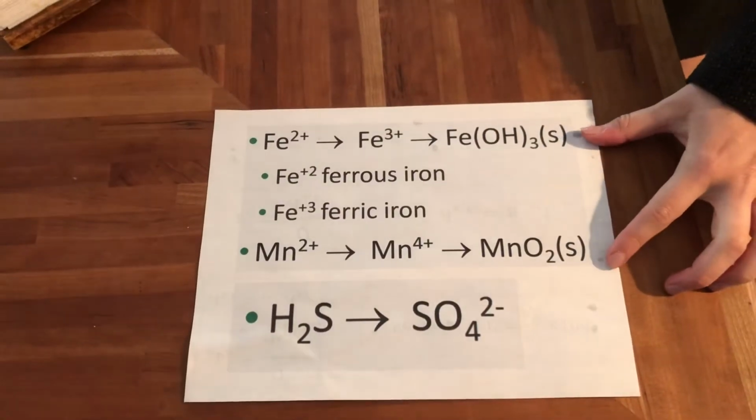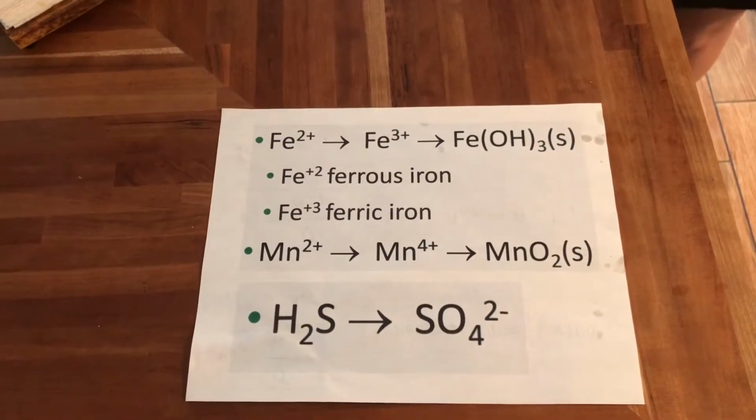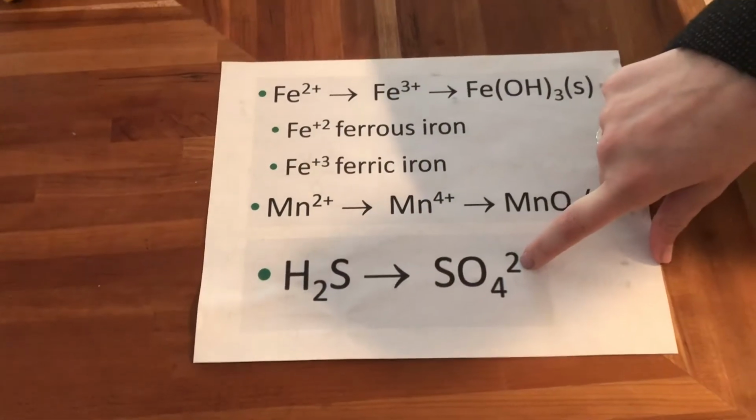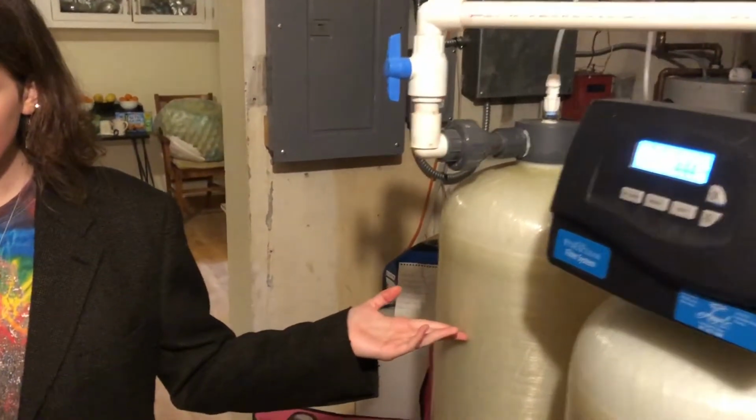As you can see from these two equations, aeration uses oxidation to remove iron and manganese from the water. It also removes hydrogen sulfide from the water. The next step of pre-treatment is chlorination. You might be wondering why we add chlorine at the beginning of the plant. This prevents the growth of algae, which may interfere with treatment of water and cause taste or odor problems.